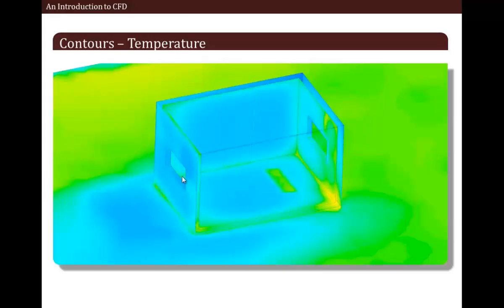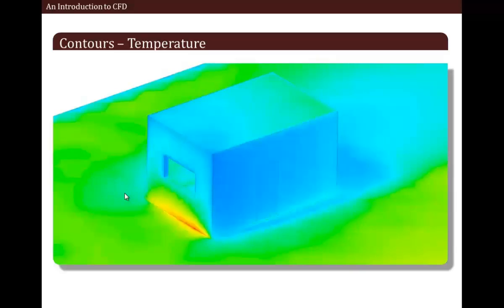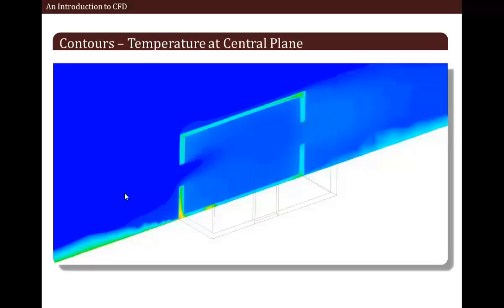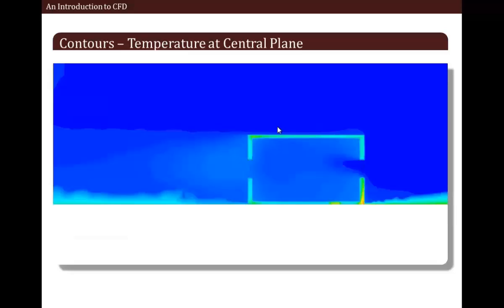With flow coming from the right and going towards left, we can see the temperature contours on the outer surfaces of the room. Looking from a different angle, here the flow is coming from left and going towards right. Now we are looking at the contours of temperature at the central plane. We have low temperature at the inlet — that is the air temperature — and then it is growing inside the room due to solar loading. One more thing we can see from this contour is the wall conduction effect.